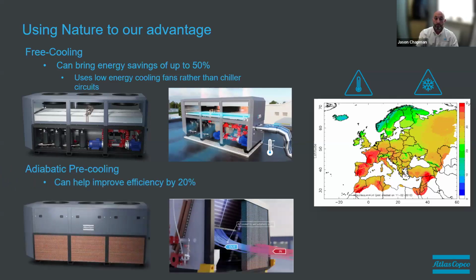So pre-cooling is where we use a water system to pre-cool, as you can see on your screen there, the bottom left-hand corner, the brown pads. It's like a cellulose pad. As the air passes over these dampened pads, it cools and then goes through the cooler. So the chiller circuit or your free cooling circuit does not have to work as hard to get the same output temperatures that you need.